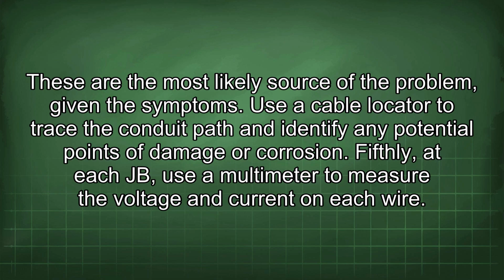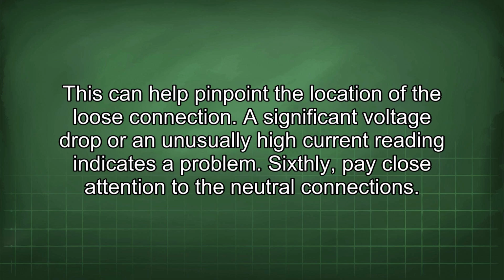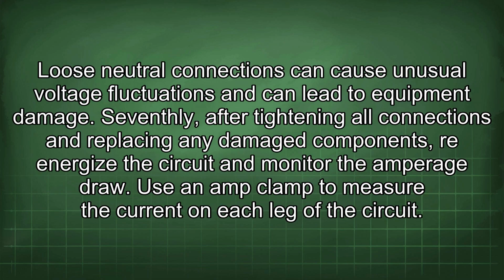Fifthly, at each JB, use a multimeter to measure the voltage and current on each wire. This can help pinpoint the location of the loose connection. A significant voltage drop or an unusually high current reading indicates a problem. Sixthly, pay close attention to the neutral connections. Loose neutral connections can cause unusual voltage fluctuations and can lead to equipment damage.